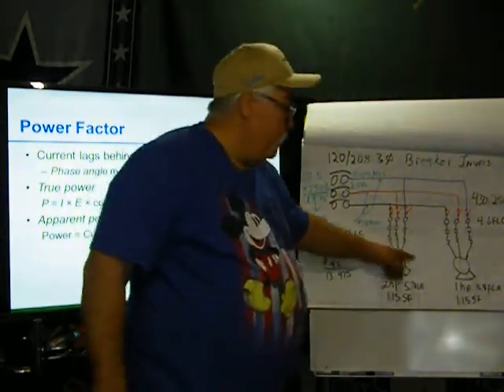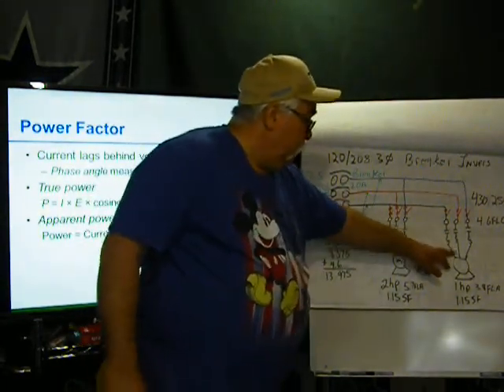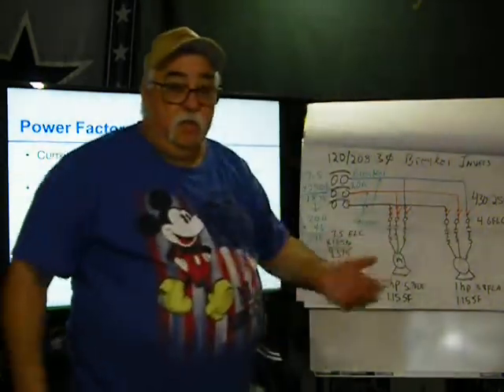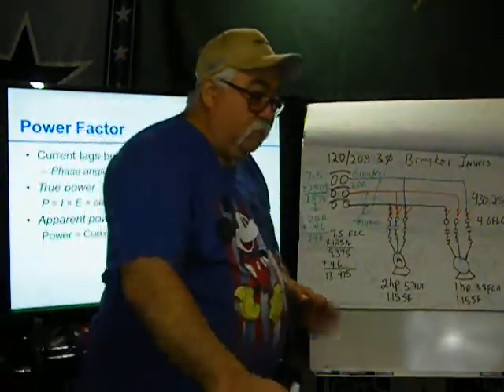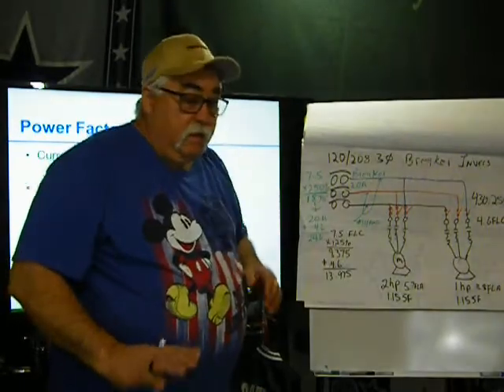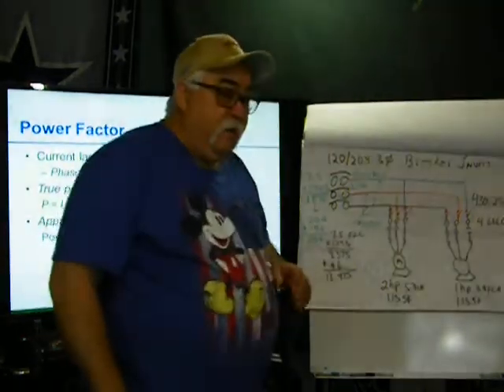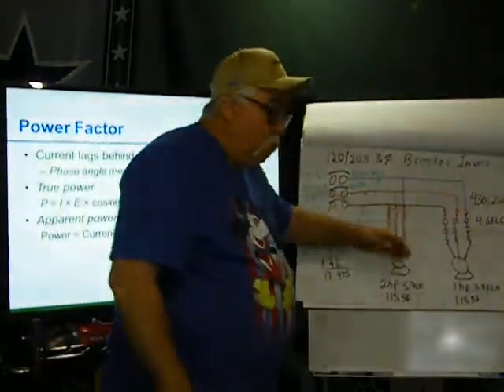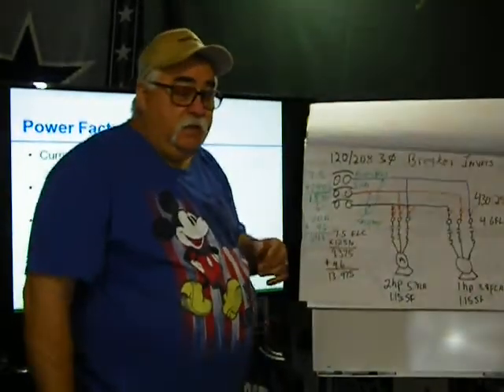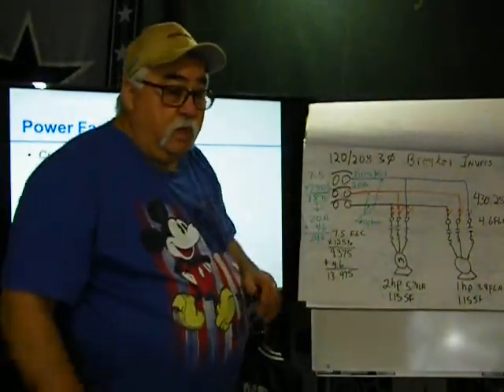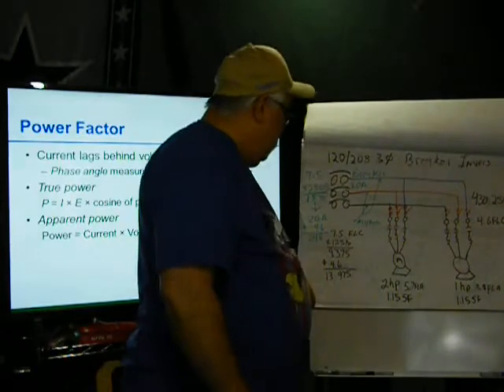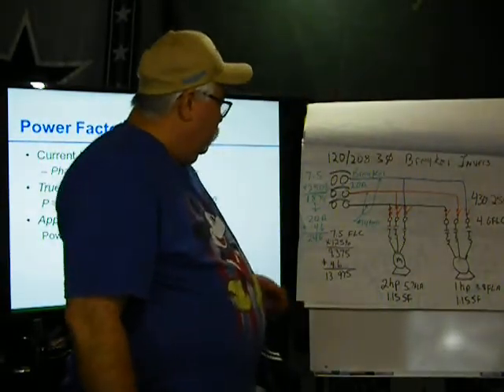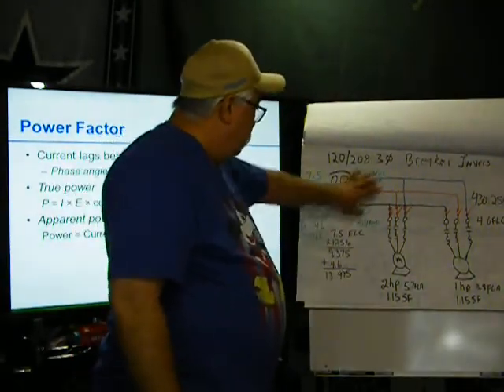I could use an 18 gauge because these overloads are protecting this wire so it doesn't get more than what the capacitors are. That's a different story. Wait till you get out in the field and you can learn that. For now, we're just taking the normal wire size that we need. Code says the smallest building wire is a 14 gauge. That's where we're going to stay. Alright? So now it comes up here. So I need a 14 gauge wire.